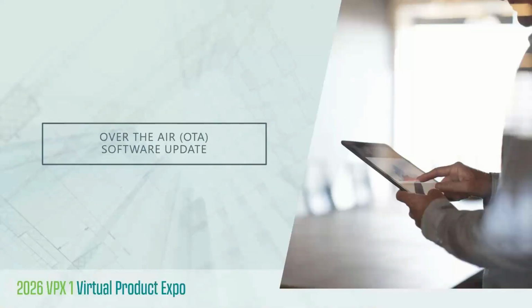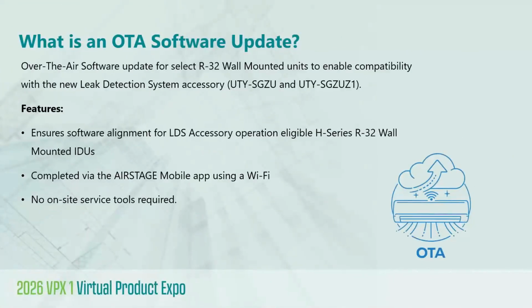Now let's talk about the OTA software update. What is the software update? The OTA software update is pretty much like a software update that you download to your cell phone, right? The OTA software update is for select R32 wall-mounted units to enable the compatibility between the LDS accessory and the indoor unit. Now, the software update will be done through Wi-Fi. So if the wall-mount unit does not have a built-in Wi-Fi, you'll have to get the Wi-Fi adapter to make sure that the indoor unit is connected to the Wi-Fi. And there's no other tools that are required to make this over-the-air software update happen.